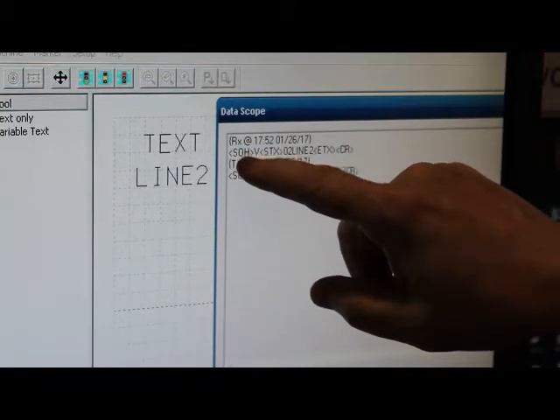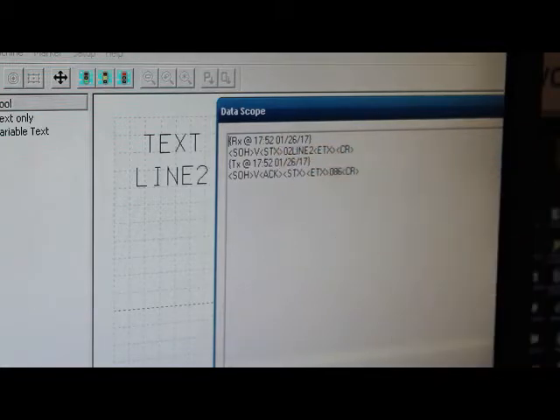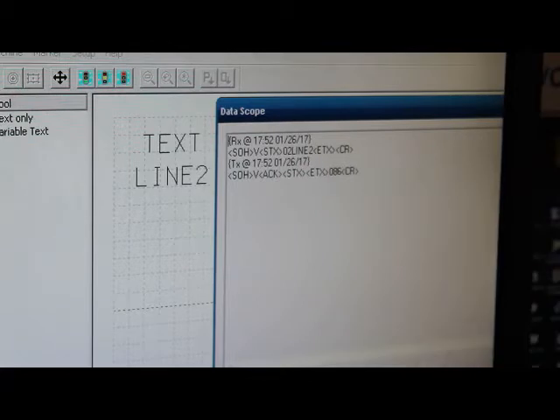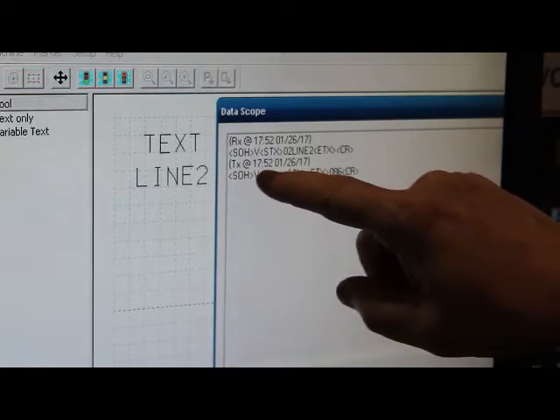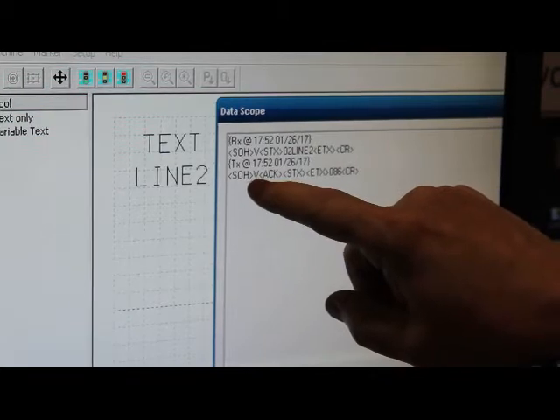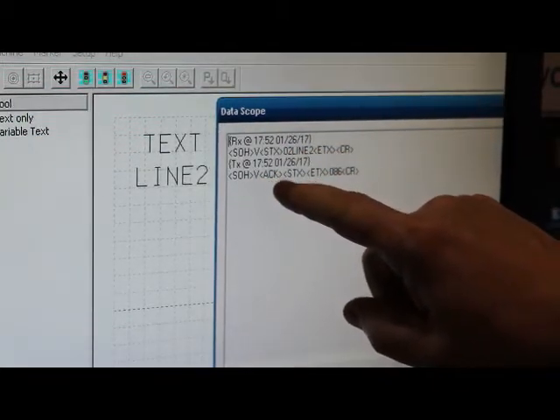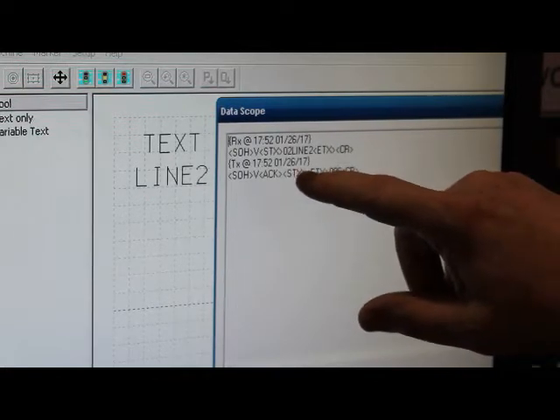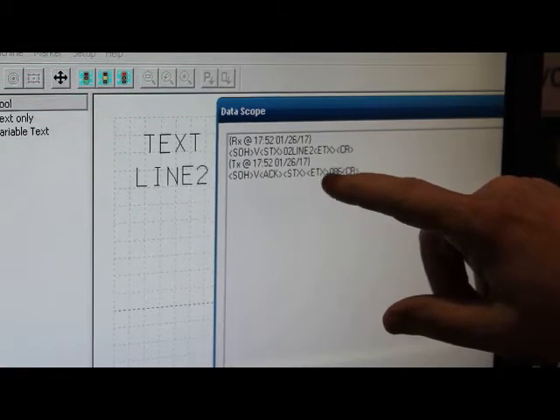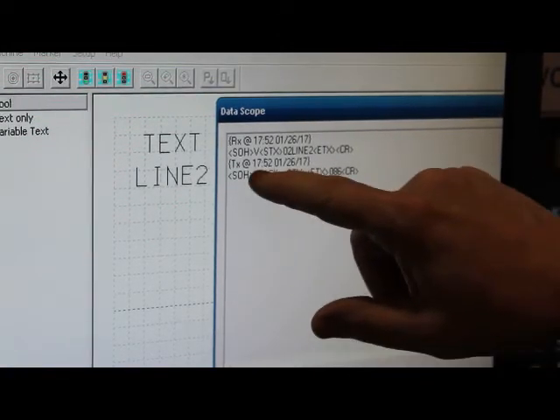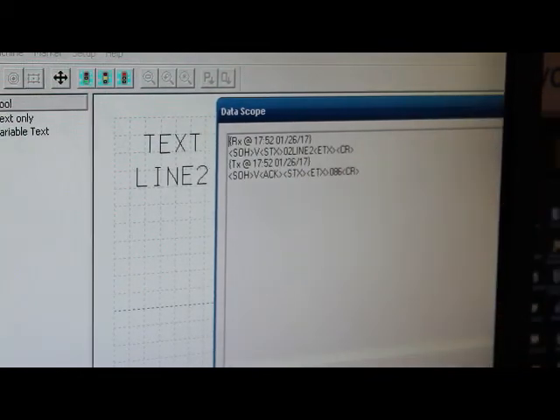These show up like this because these are, in this case it's ASCII number one, ASCII number two, and those are non-printable characters. So it just shows the start of header as a representation of that. Then it tells me that it sent back, at the same time, start of header, the variable, acknowledge, which means yes we did receive it okay. Start of text and end of text, it's not really sending any text back. The ASCII equivalent of this V and the carriage return, which is the terminator.